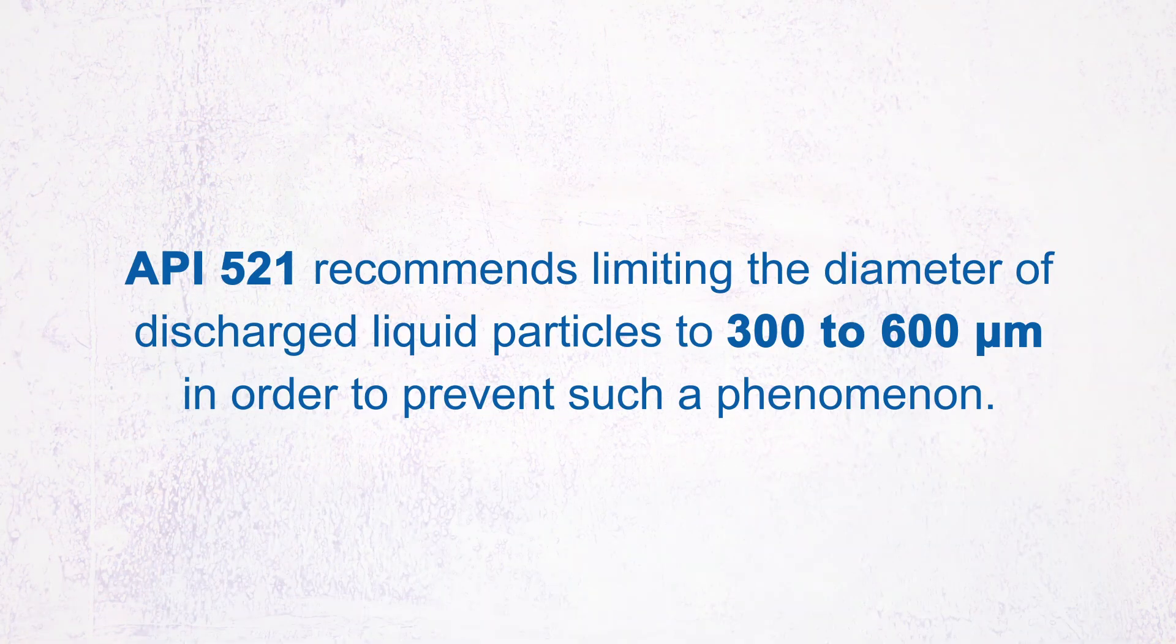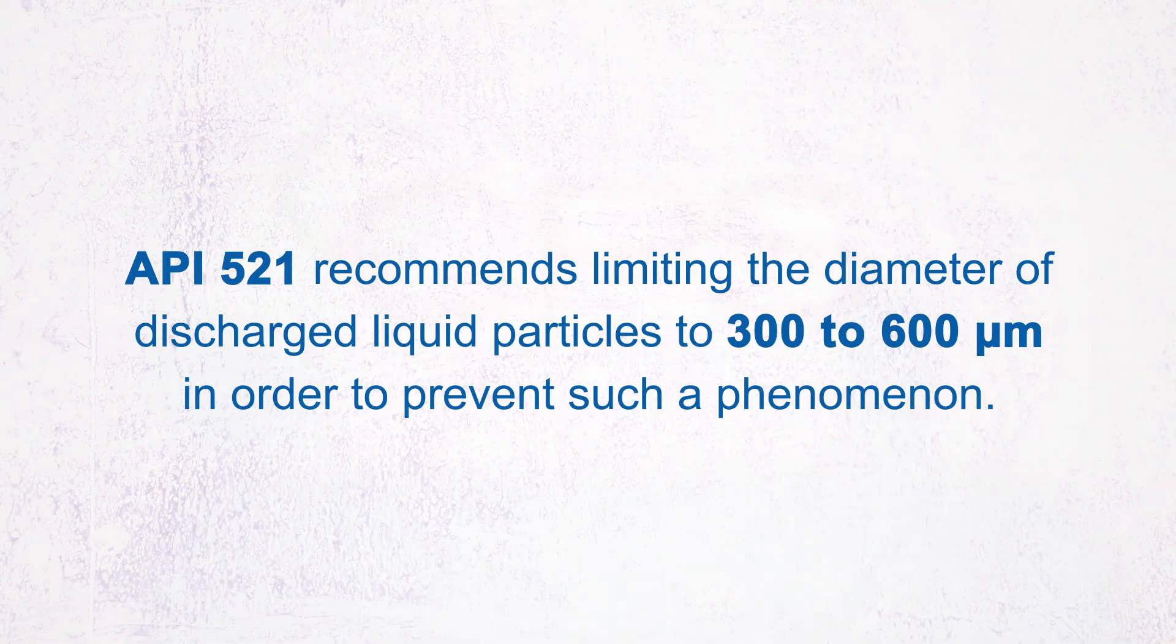API 521 recommends limiting the diameter of discharged liquid particles to between 300 to 600 micrometers in order to prevent such a phenomenon.